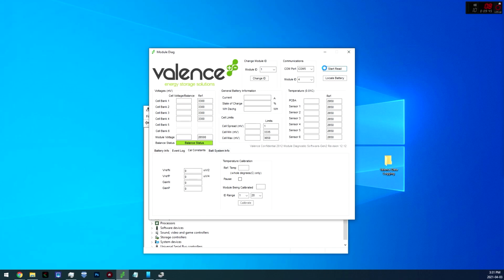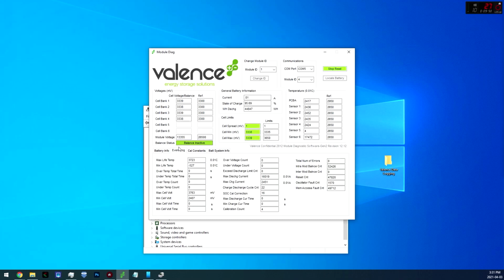Okay, so I'm gonna go back to start read, and we're gonna go back to this tab. So this is the event log. This is gonna give you a bunch of events. It's an event log. So this is going to tell you the max life temperature and the minimum life temperature, so the highest temperature the battery's ever experienced, and the lowest. So you would multiply that by 0.01, giving you 37.23 degrees and minus 5 degrees. And you have all these other values here. You can have a read here. Millivolts, so this would be 3.7 volts and 2.4.